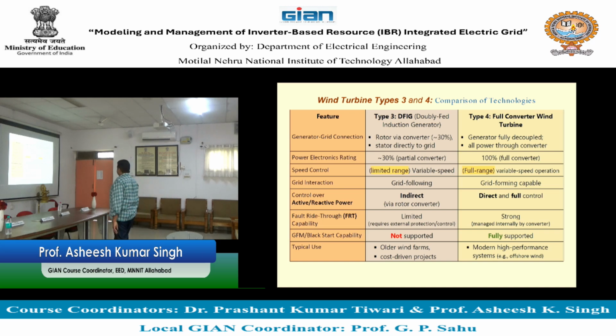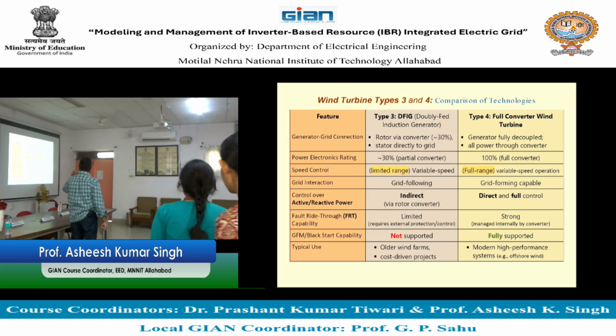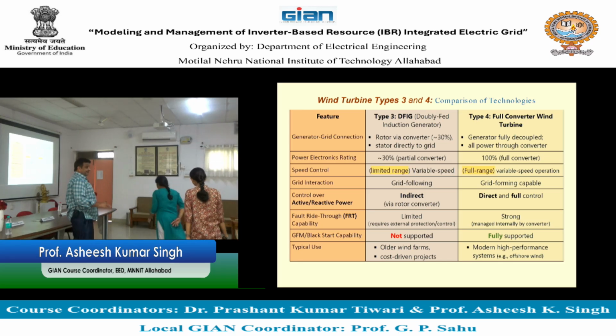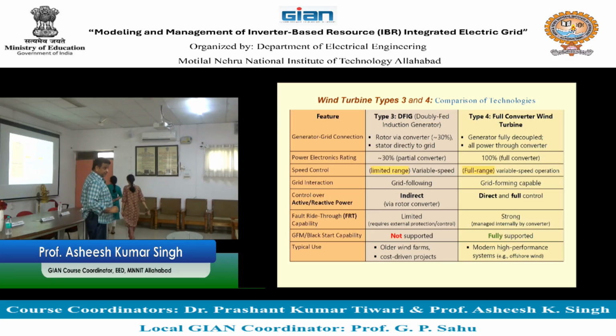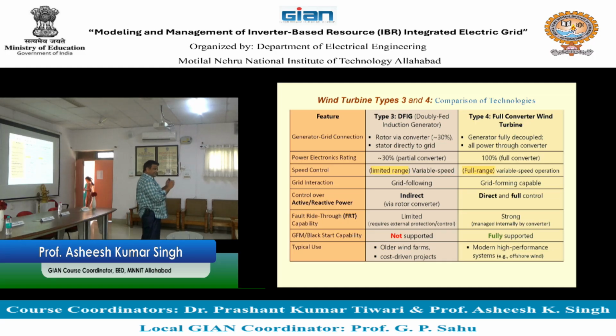So what is the difference? First feature is generator grid connection. In type 3, only 30% power is processed through the rotor via converter, while the stator handles 70% power directly to the grid. This 30% is only managed or controlled, adding flexibility to wind power generation. Whereas in type 4, the generator is fully decoupled and all power is processed through the converter, so it is fully controllable.